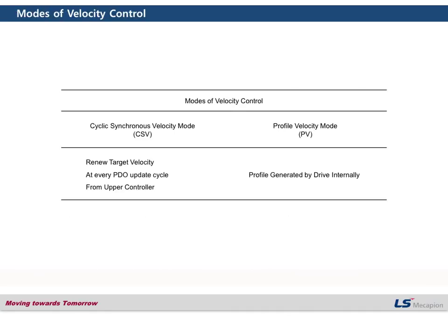The significant difference between the CSV mode and the PV mode is the PDO update cycle. In the CSV mode, the drive renews the target velocity at every PDO update cycle. However, in PV mode, the drive doesn't need PDO update — the drive generates the profile by itself.